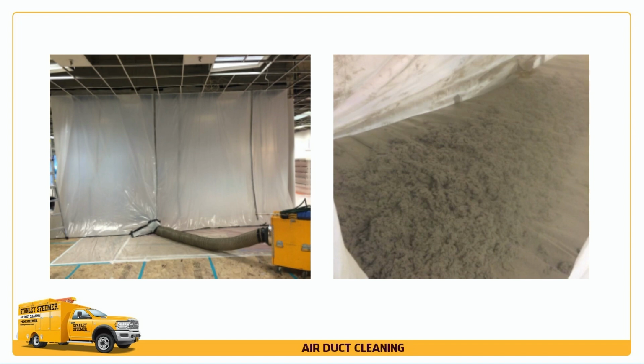So what happens is they say it's more efficient. They'll have these lights with little openings inside, and all of that air gets sucked in there because they have a fan way up on the roof pulling air in. So the easiest, least expensive way is to say, hey, the drop ceiling, we're going to use this as an open plenum return. So all of the dust accumulates and sits there, and guess what happens when it gets in above the drop ceiling? It goes back up there and just falls.